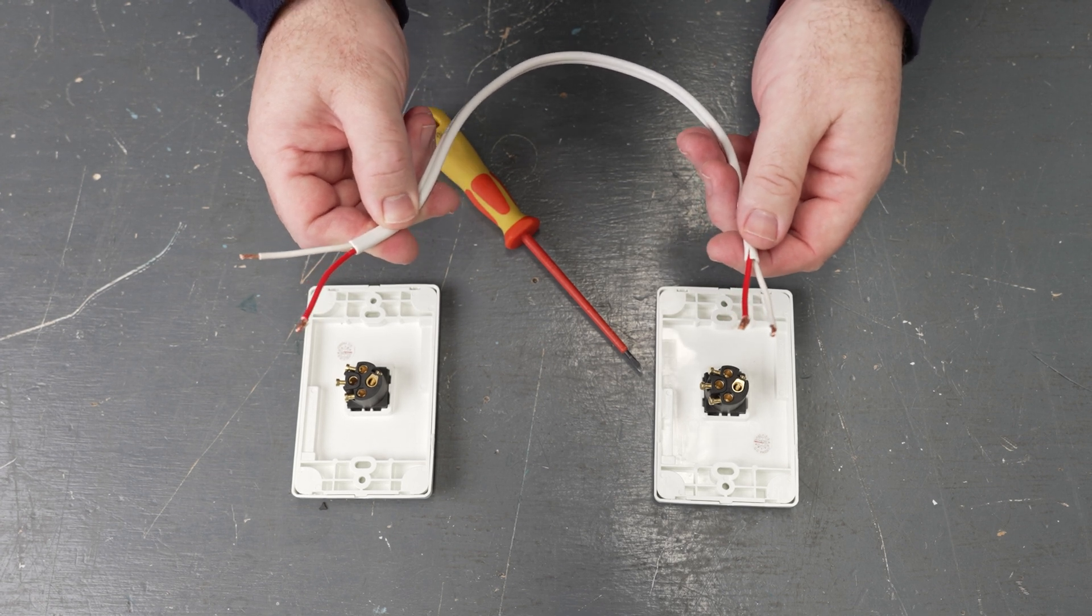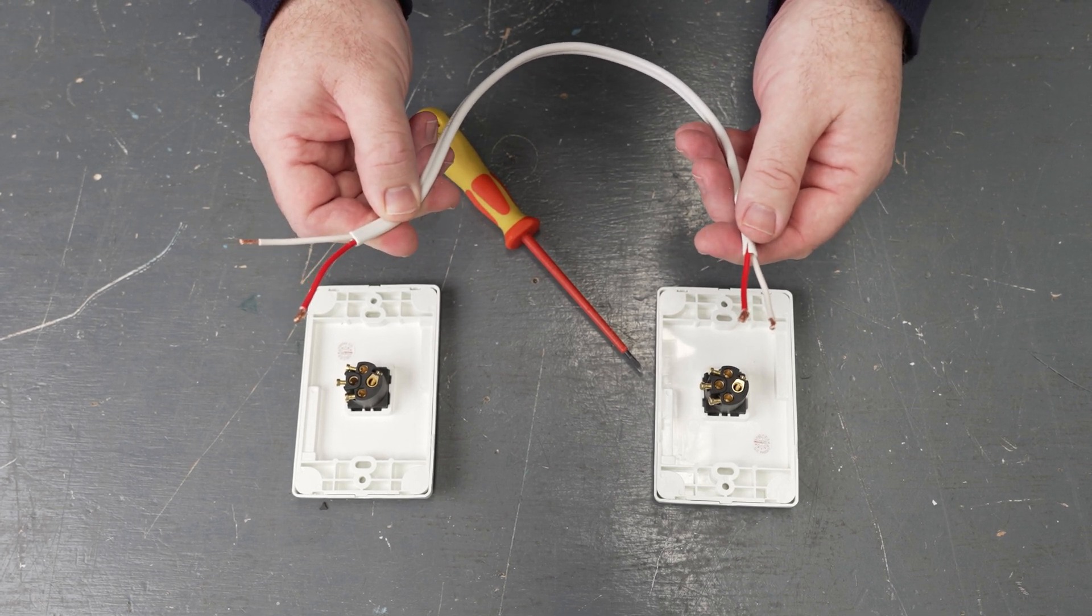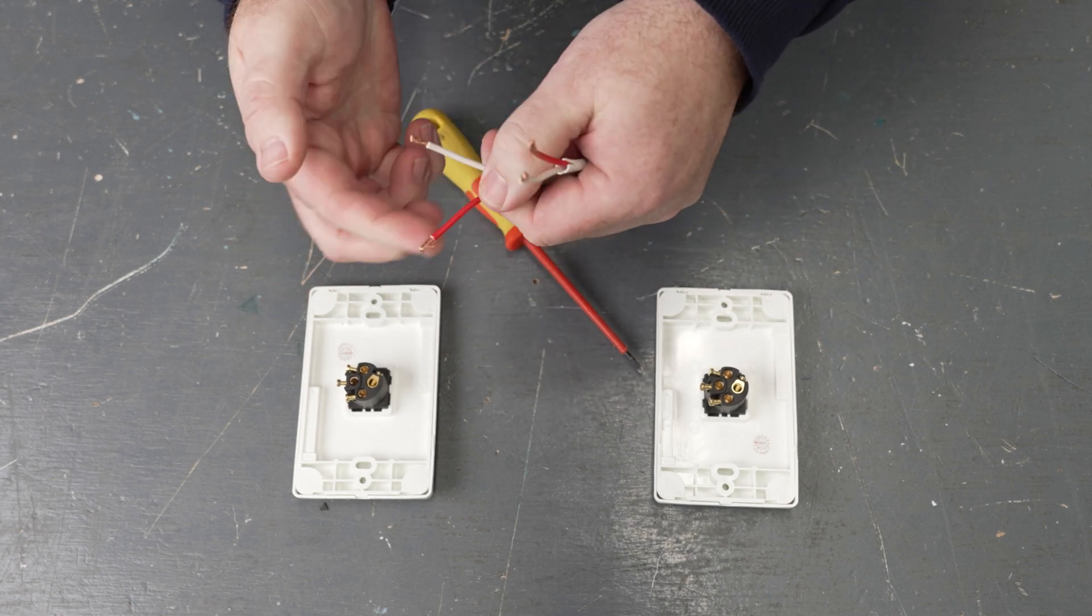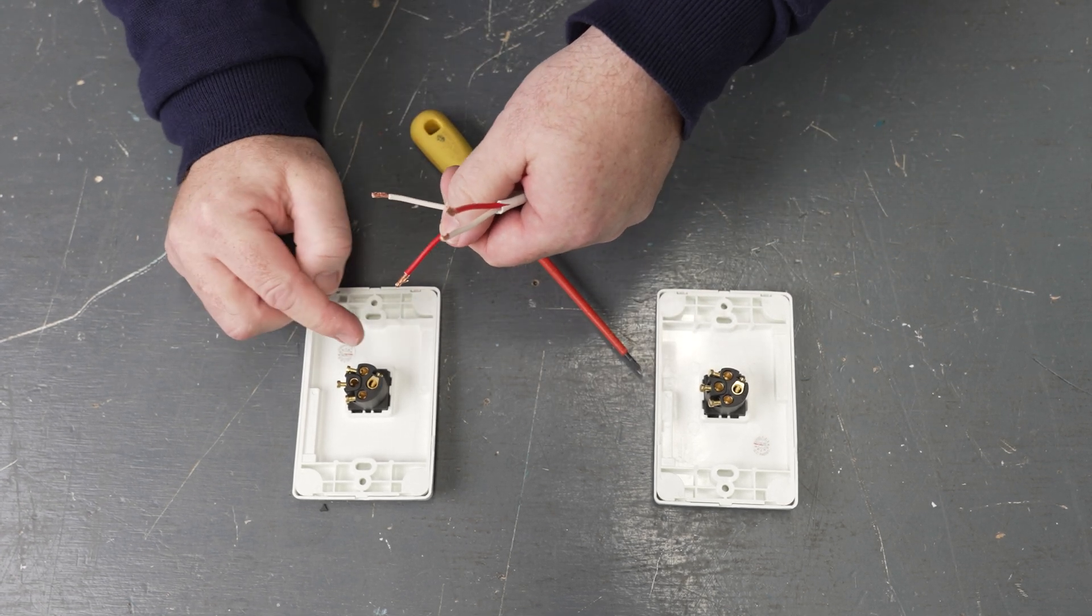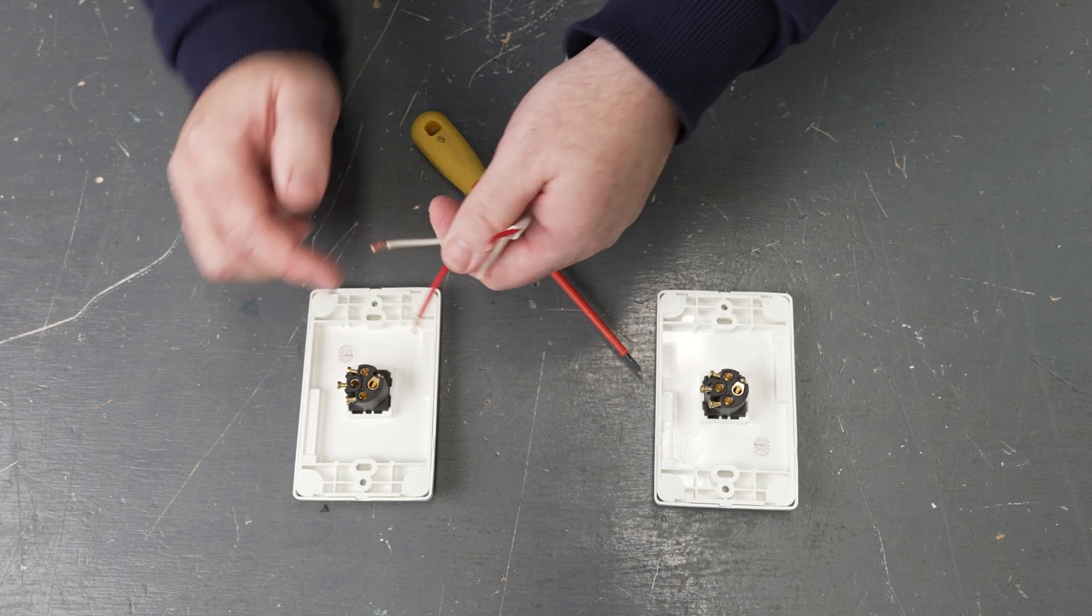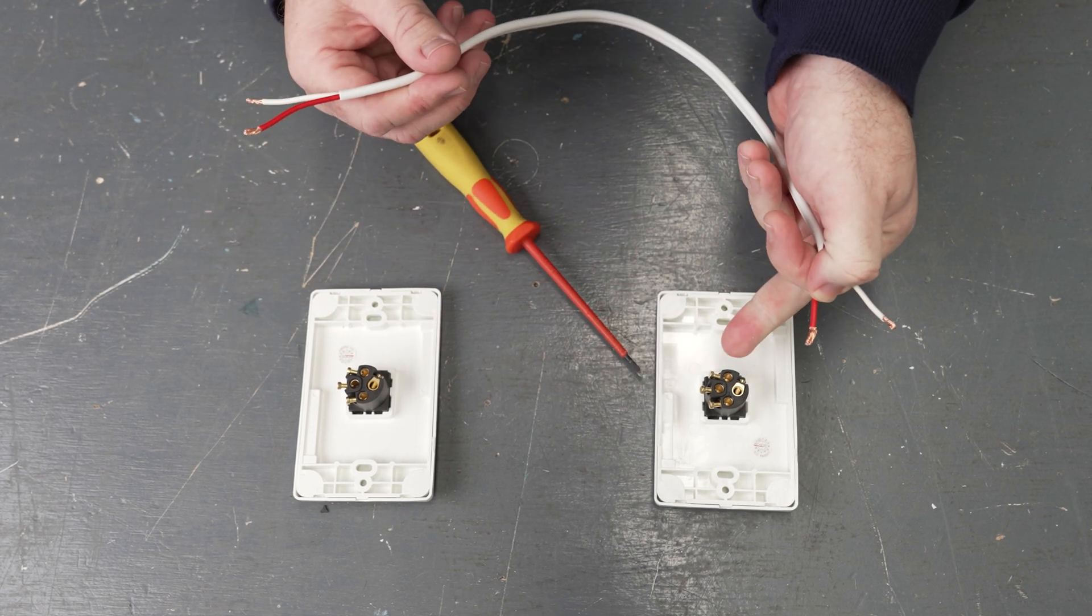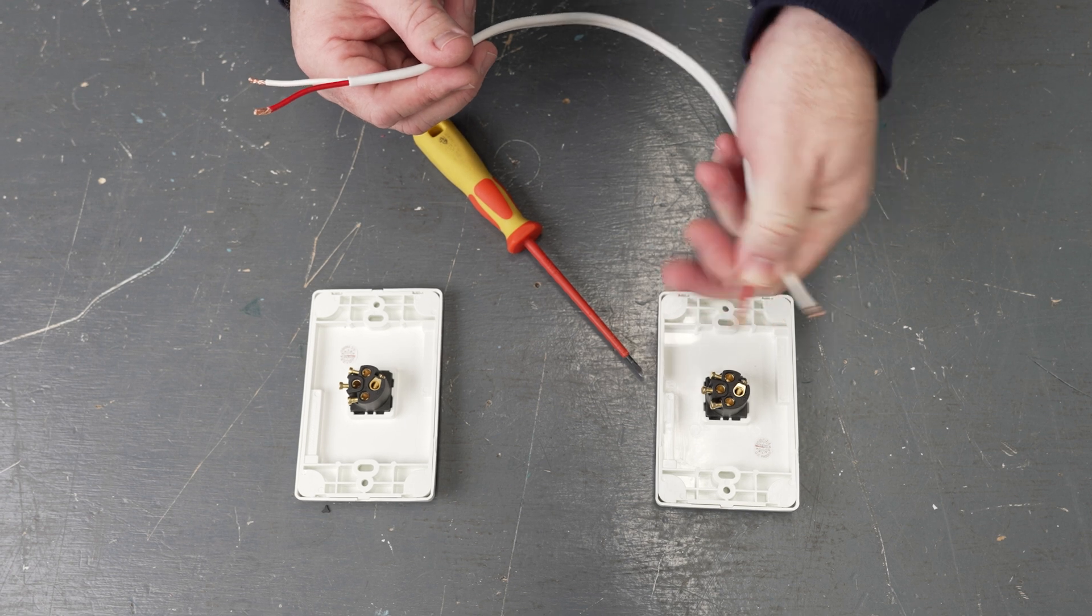As per our drawing, we're going to be using a strapper cable between the two light MECs. In this case, this is a twin active. We're going to take the red conductor and terminate it into the number one terminal. The other end, we'll do the same, making sure to put it into the number one terminal.